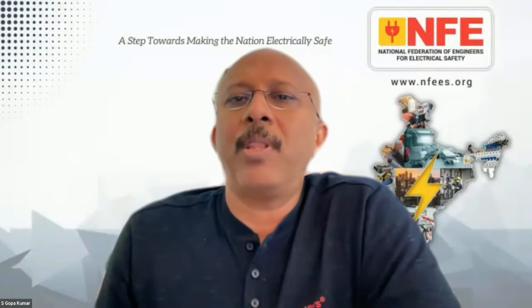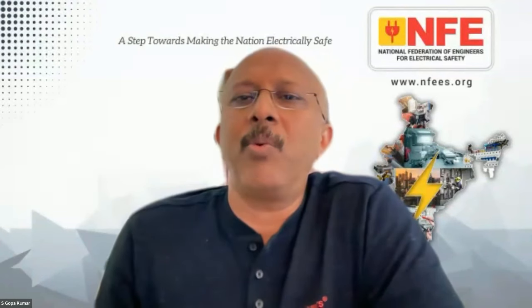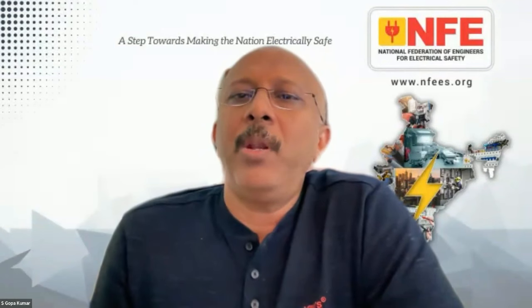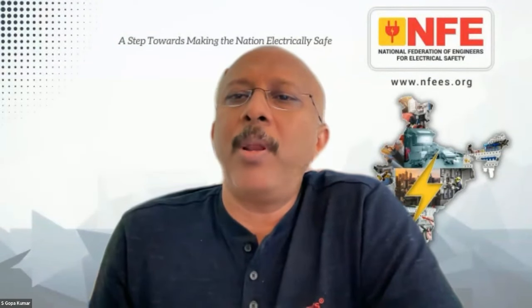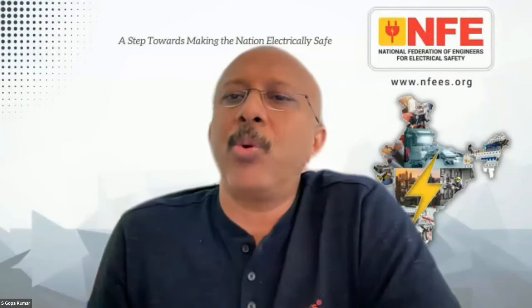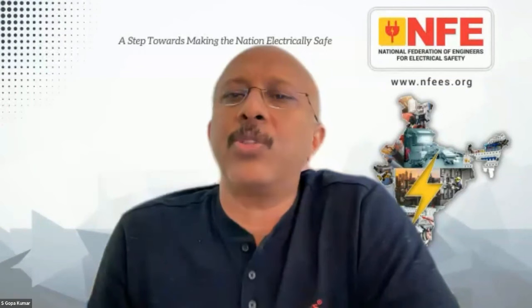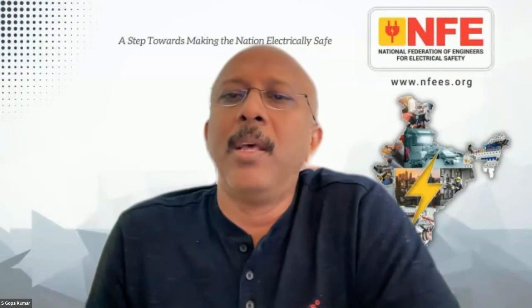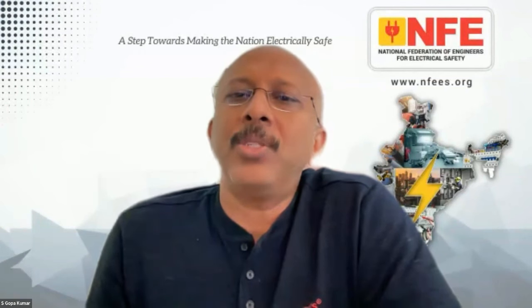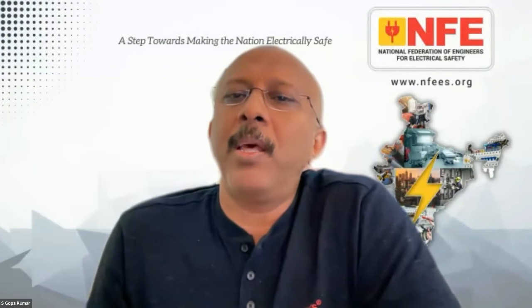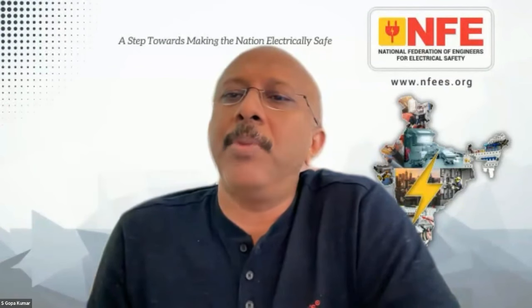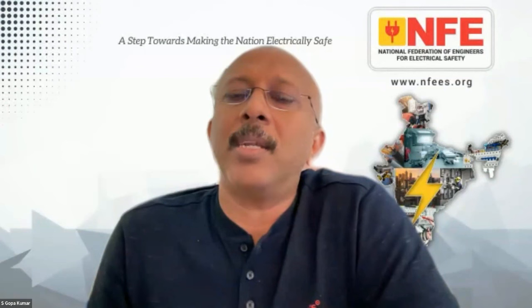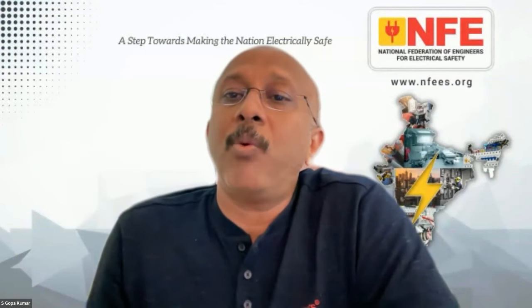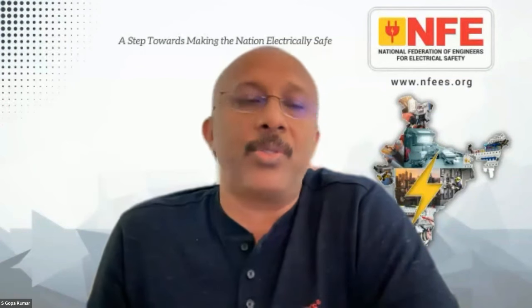So thank you very much for that answer. Now we have a question from Mr. Ulas Vajray. When we talk about equipotential bonding, even connecting gas and water pipe as shown in the figure shown by Mr. Paul Meenan, however, IS-1646 clause 8.2 states that in no case shall gas, steam, sprinkler or humidifier pipes be used for an earth connection. So is it not a violation of this clause?